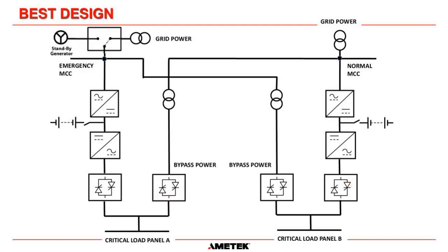And then, unlike a parallel redundant UPS, we have 2 critical load panels. So even if one of the critical load panels fail, or if the cabling between one UPS and one critical load panel failed, we still have critical load panel B operational. So this is by far the most robust design of UPS system that you can design for redundancy. Now, the only thing that you have to be careful with these types of systems is that you do match the load panel down here. So the loads on load panel A should all be repeated on load panel B.